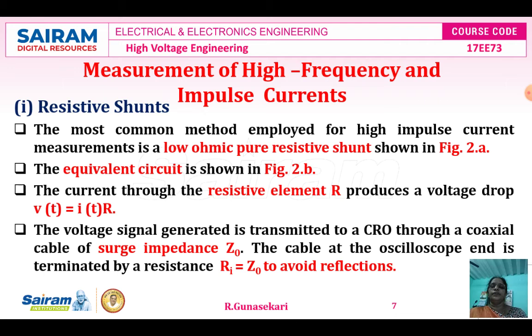The equation V(t) = I(t) × R is the time domain equation. The voltage signal generated is transmitted to the CRO through a coaxial cable of surge impedance Z₀. The cable at the CRO end is terminated by resistance r_i equal to Z₀ to avoid reflections.